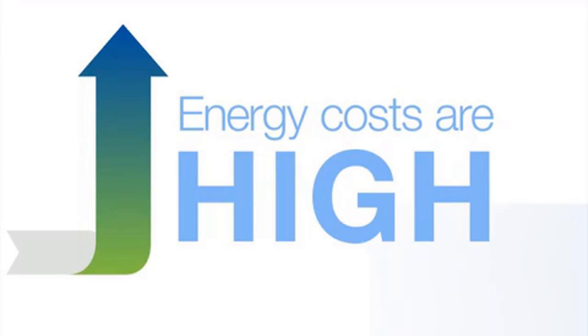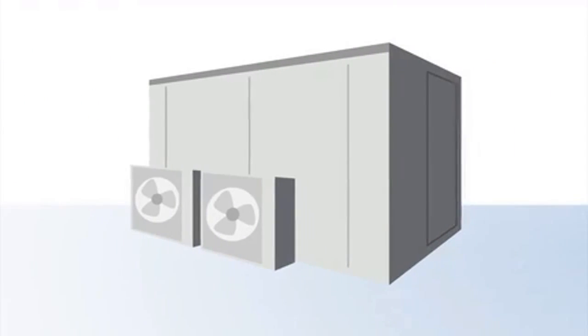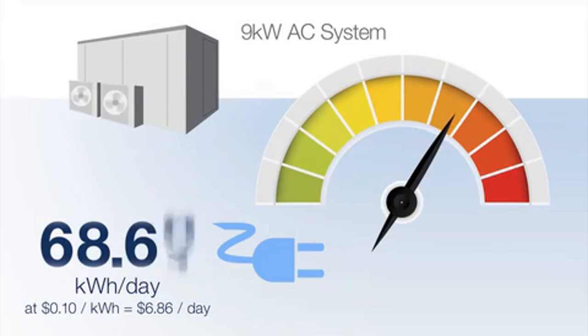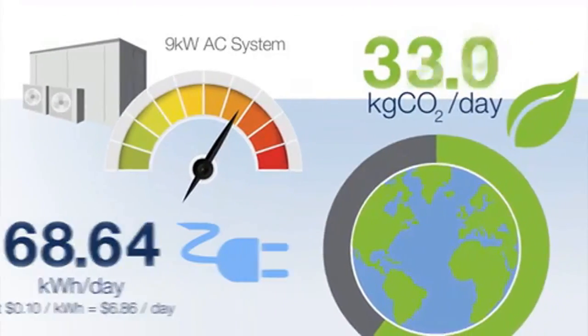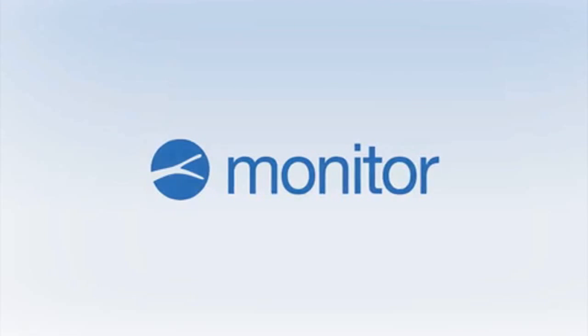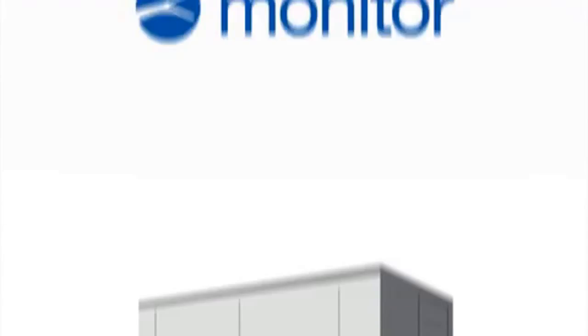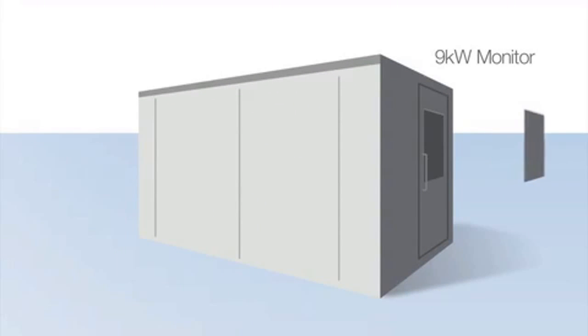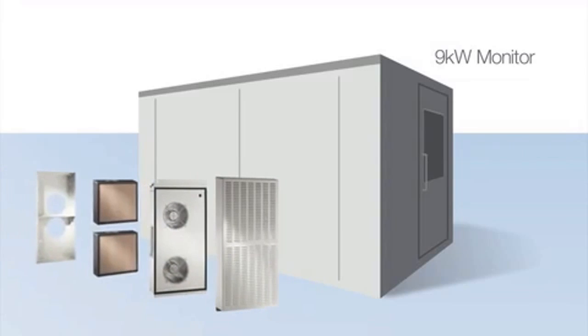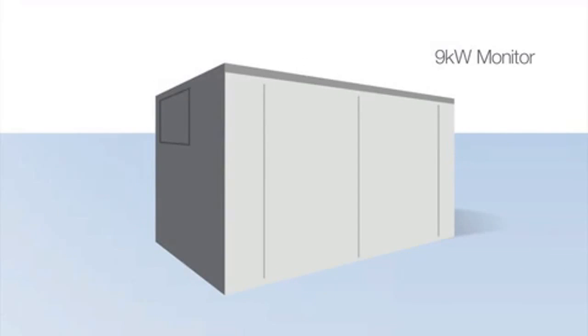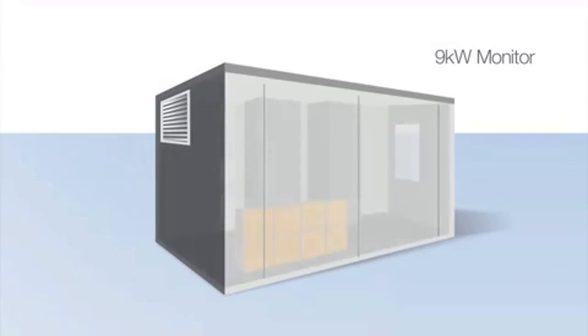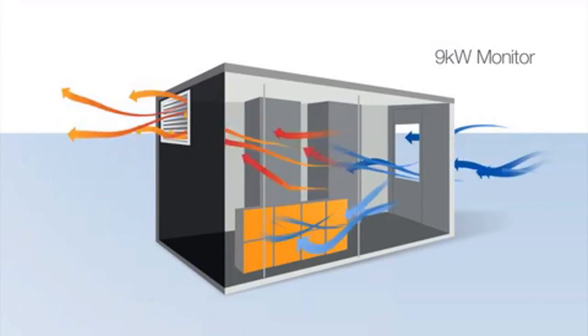Energy costs are high. If you're running air conditioning units for equipment cabins or looking to fit newer units to comply with regulations, you may be wasting money. Every day, the cost of maintenance, electricity, and the subsequent cost to the environment in CO2 emissions will add up. There's a better solution. Alifab's monitor is an easy-to-fit, completely integrated system that drastically cuts your energy consumption. The system draws in external air through unique hydrophobic filters. High-performance, backward-curved radial fans create a positive pressure, which forces hot air out of the cabin through a damper. The result is controlled and maintained air temperature at a fraction of the cost of air conditioning.